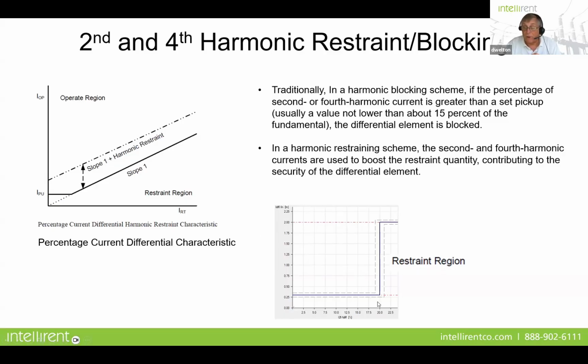And this is what it looks like right here. This one was set at 20%. And you'll see that if we have greater than 20% harmonic component, this is your restraint region. If it's less than 20%, that means that you're just operating under normal circumstances. You have a fault in the transformer, and the 87 element is going to trip.